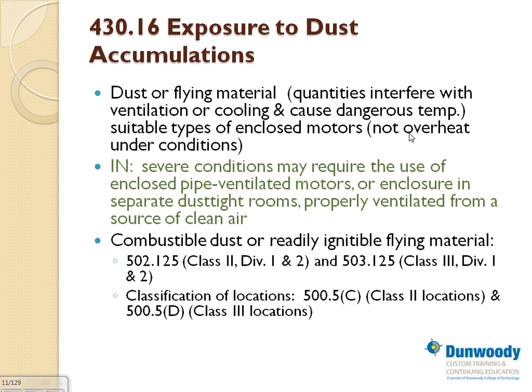I don't know if you have a situation where you even have to use pipe ventilated motors, enclosed pipe ventilated motors, enclosures you can use in very heavy, severe conditions where there's a lot of dust. And again, these are dust, but not combustible dust. Combustible dust would move you all the way to hazardous location. These are just dust. So if you have a very dusty environment, you have to choose the right enclosure. And if it's very severe, you have to have enclosure pipe ventilated motors. Do you guys have anything that pipe ventilated motors to the outside?